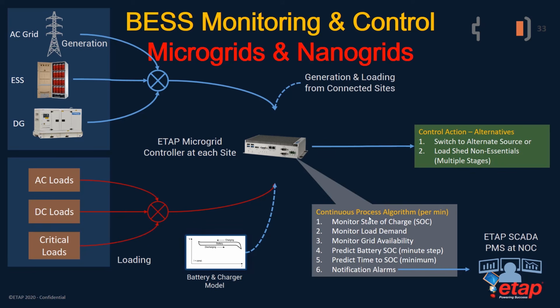And using the controller logic, we continuously process at every step the state of charge, the load demand, and the grid availability, and based on that we predict the battery state of charge. We predict the time to minimum state of charge, that is when the battery is going to be fully discharged, and then we send notifications accordingly to the network operating center or the ETAP SCADA PMS that is situated at the network operating center or the control room. The controller is also able to send out control actions or alternative actions, such as switching to an alternate source in case the battery state of charge reaches minimum value, or it can also shed loads or non-essential loads in multiple stages to preserve the state of charge of the battery and extend the battery life as long as possible.